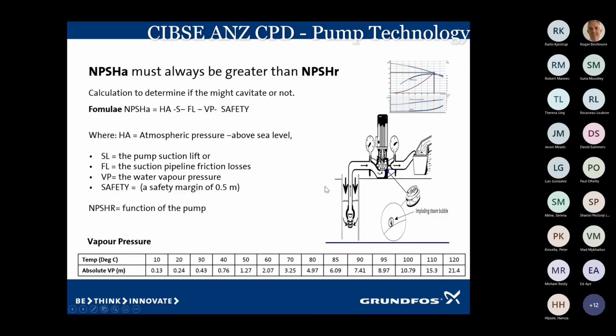And on the pump curve up the top, you can just see we've got our performance curve, we've got our hydraulic efficiency curve. In the next box down, we've got our power curve. And the next one down is the net positive suction head required. And the pump manufacturer must give you that curve. That indicates the net positive suction head required at that given flow rate.